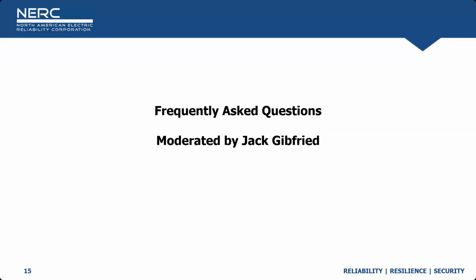We saw in some of the Dominion events, and the subsequent results from Dominion speaking with their large load customers, that they were able to resolve a lot of the trip-outs for multiple minutes by coordinating the protection settings within the facility.